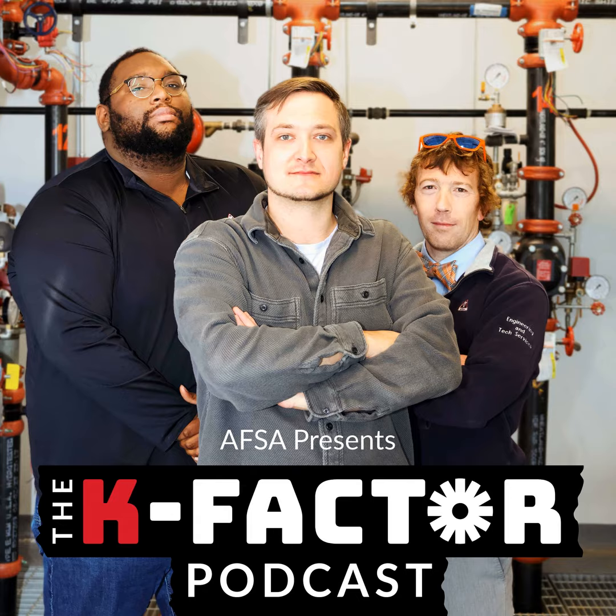So what makes this product Automist? Okay, so the biggest difference with this system is we interlink the system with a smoke detector. And we use a smoke detector to initiate the system to come out and look for the fire. So the other big difference with Automist compared to a traditional sprinkler system is we put our nozzle on the wall instead of on the ceiling. And the reason we do that is because of the way water mist works compared to a sprinkler system, we want to try and get as much of the mist directed at the fire as we can, as opposed to wetting all the surfaces and using that to suppress the fire.